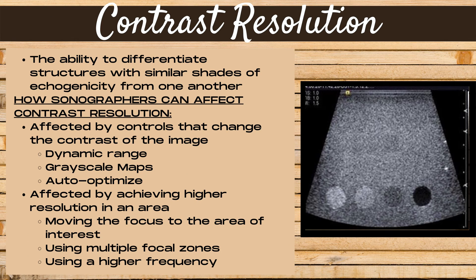Contrast resolution is the ability to differentiate structures with similar shades of echogenicity from one another. Contrast resolution is affected by controls that change the contrast level of the image, such as dynamic range, grayscale maps, and auto-optimize. It is also affected by achieving higher resolution in an area — moving the focus to the area of interest increases lateral resolution, which in turn increases contrast resolution. Using multiple focal zones and a higher frequency also improve contrast resolution.